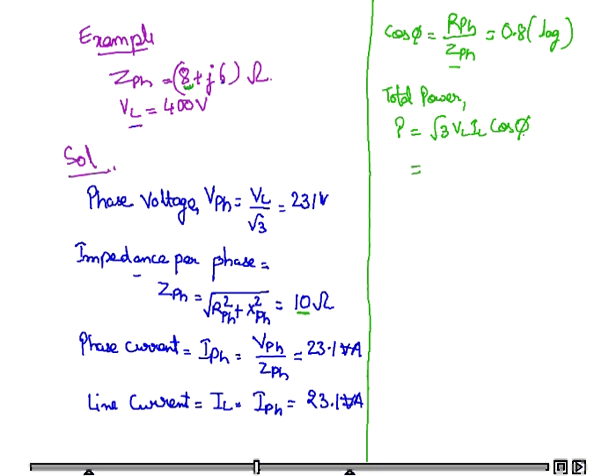Total power is root 3 times VL times IL times cos phi, where VL is 400, IL we have calculated is 23.1, and cos phi we have calculated is 0.8. Substituting the values, the value comes out to be 12,800 watts.